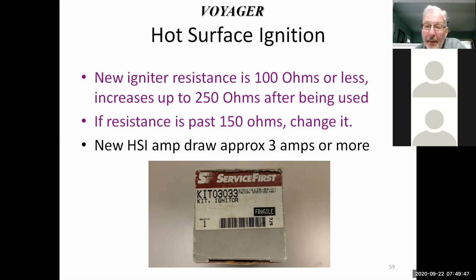So if you want to check the amp draw, or if you want to check the ohm reading on them, if they're 150 ohms or more, you probably want to change it. If their amp draw drops off to less than 2 amps, you probably want to change it. So it's not that expensive. It's a good maintenance item.